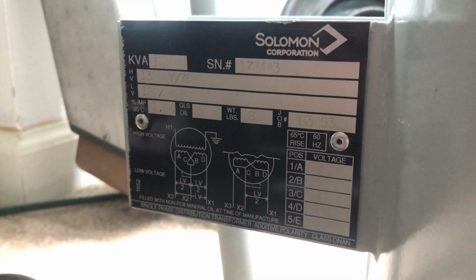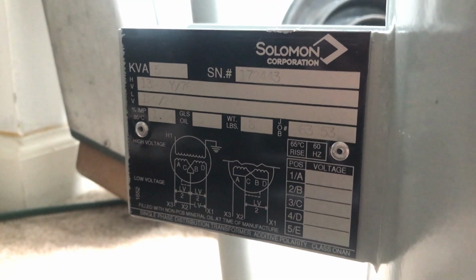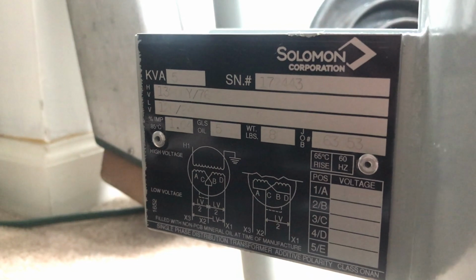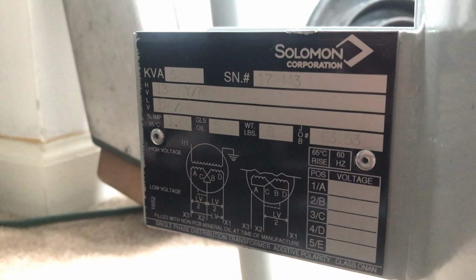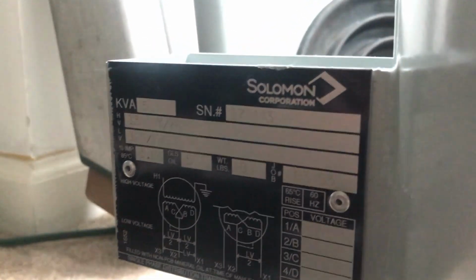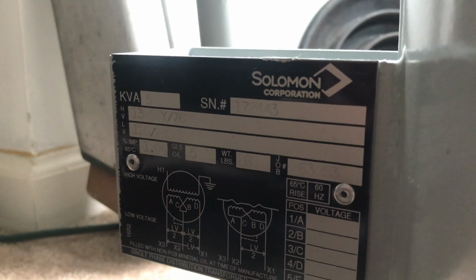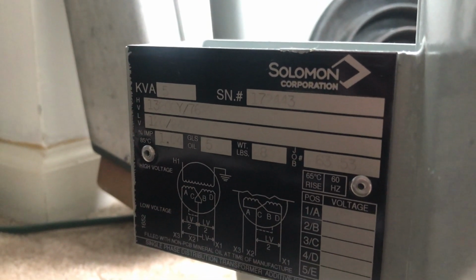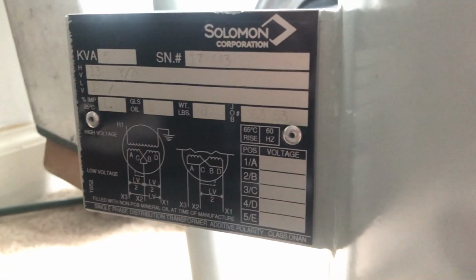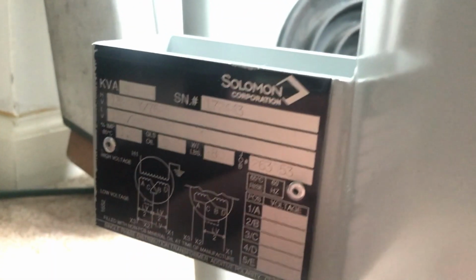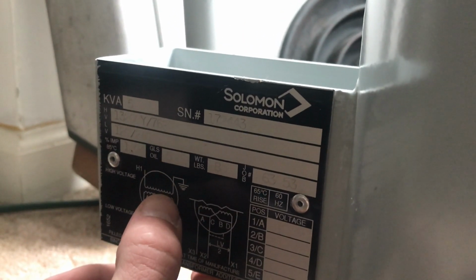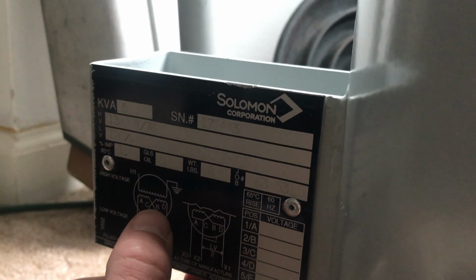As you can see, the low voltage is 120/240. Keep in mind that that is additive, so 120 plus 120 equals 240. 7620 plus 7620 does not equal 13200. As you can see in the schematic of the low voltage, you have one high voltage coil and 2 low voltage coils. Each are good for 120 volts.